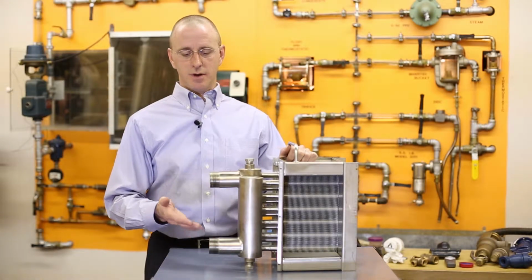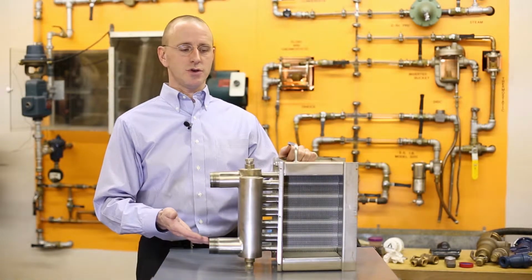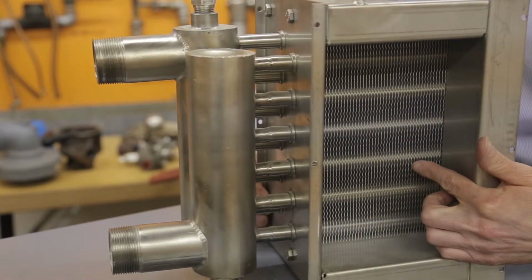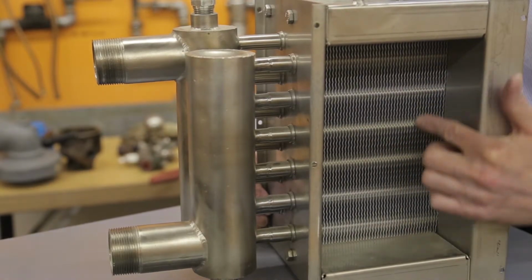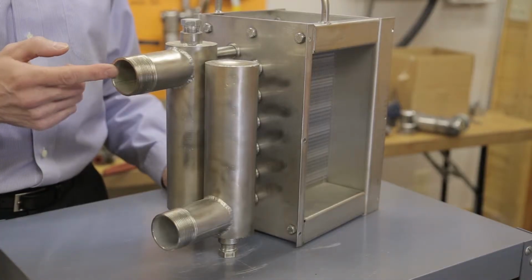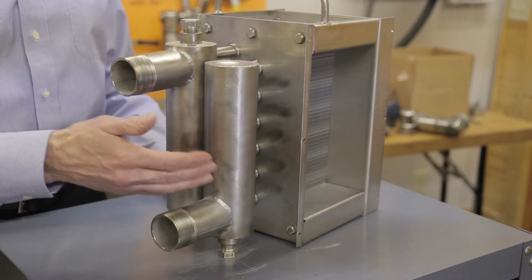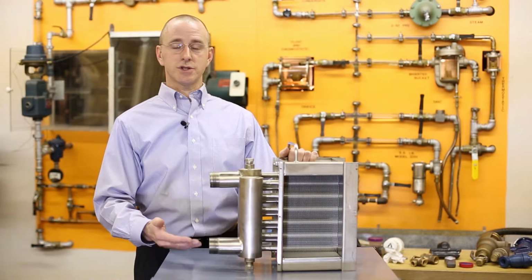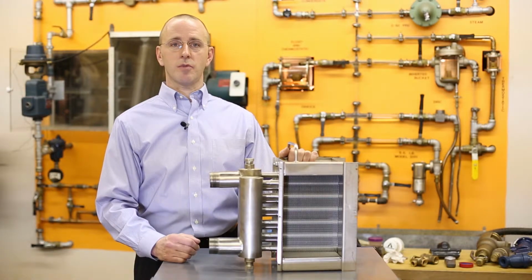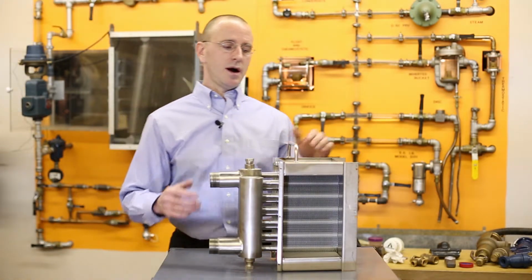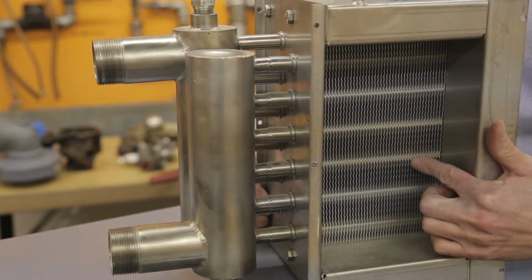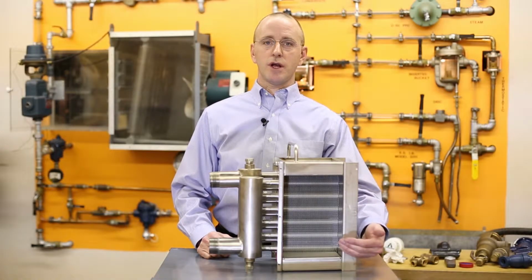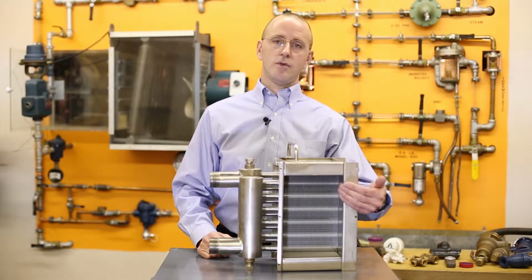For fluid coils, there's a few things that you need to keep in mind. You've got obviously a process fluid that you're using to do either your heating or cooling, and then you've got your air side that you're either cooling down or heating up. On the fluid side, we need to know what fluid it is, whether it's water or either of the glycols and what percentage the glycol is, or if it's some other process fluid, we'll need to know some of the thermal properties. On the air side, we'll need to know how much air is blowing through the coil, and obviously whether we're heating or cooling, and what the temperature is.